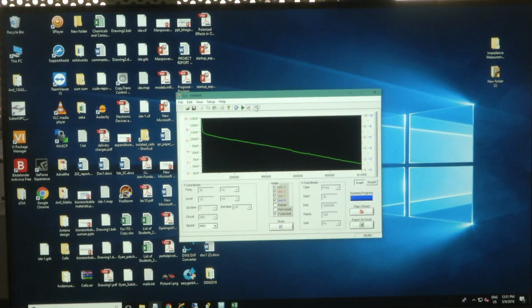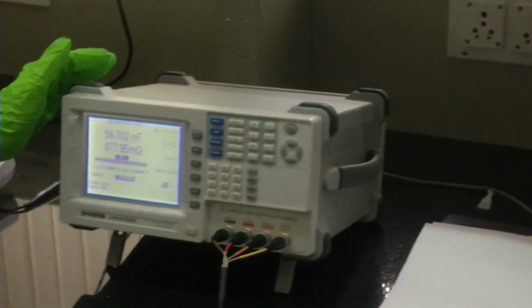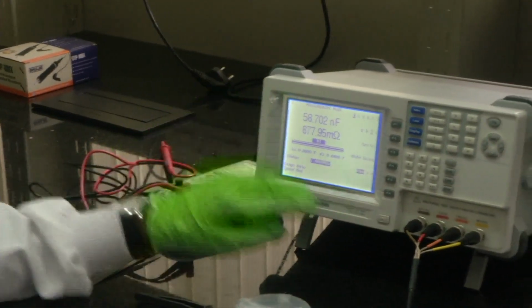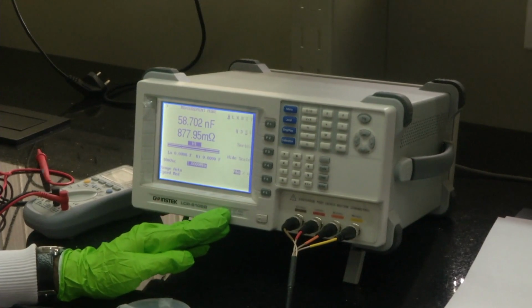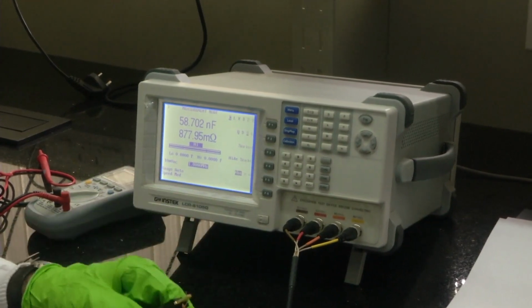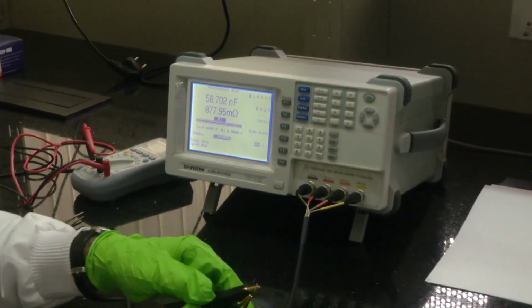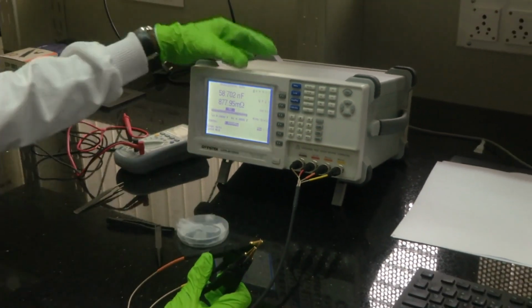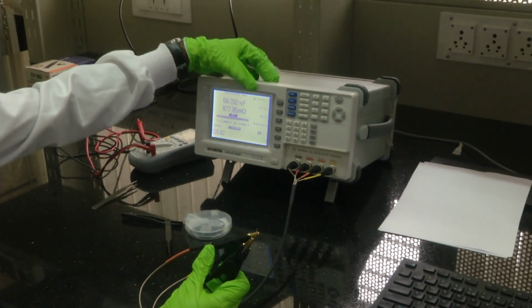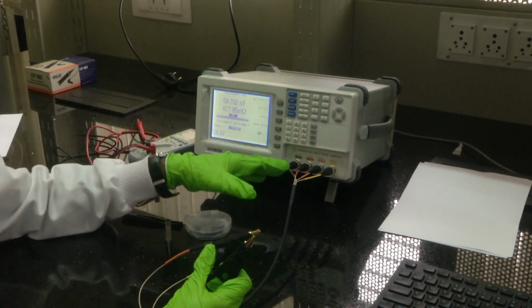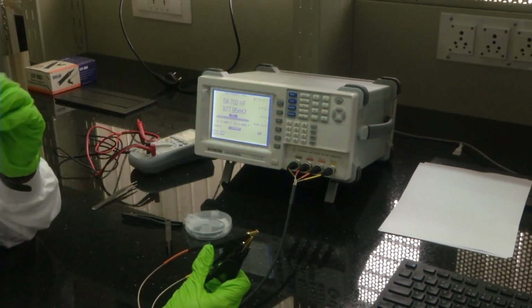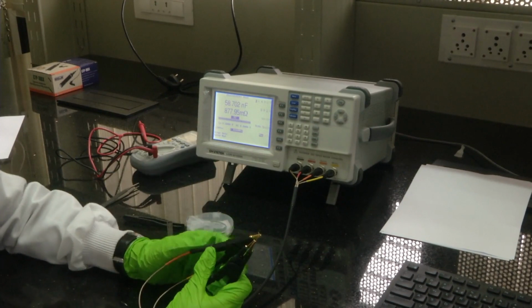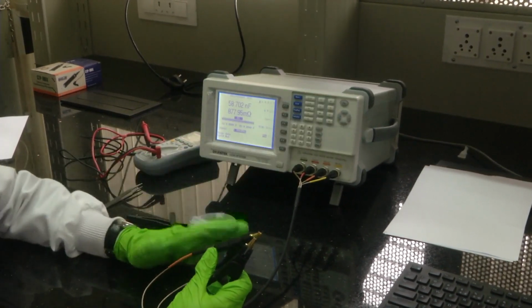So, in this module what all have we seen? We have seen how to do calibration, what the impedance analyzer is, why it is so special compared to a normal multimeter, and what frequency ranges this particular impedance analyzer can operate in. We saw what the probes do, acting as a source as well as a sense terminal, what parameters we can measure, how to do actual calibration, and how to do a frequency-wise sweep of your measurements using software that comes with the tool.